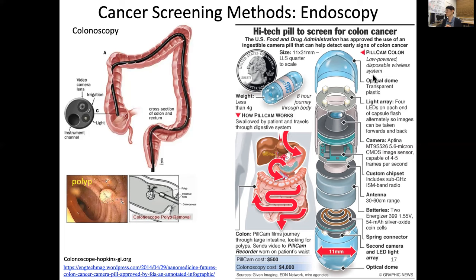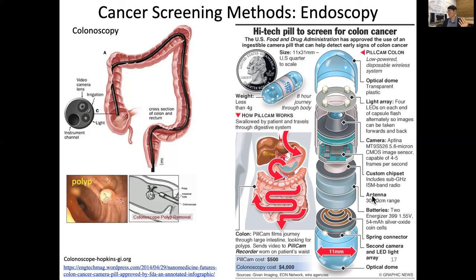The pill cam is a low-powered, disposable, wireless system. It has an optical dome, a light array of about four small LEDs for illumination, and a CMOS image sensor camera that takes about four to five frames per second. It transmits images outside the body via a radio antenna with about 30 to 60 centimeters range, and it is powered by small batteries. There is also a camera on the other side as well.